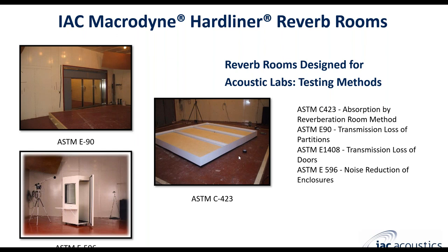The idea is to have speakers producing sound in this reverberation room. Those speakers are amplified by the reflections in the room, and the goal is to have as much echo or reverberation as possible to allow the sound to be evenly distributed across the entire volume. In theory, no matter where you put a microphone, you should have the same sound pressure level measurement inside a perfectly reverberant room. Another common testing method is ASTM E90, which measures the transmission loss of partitions — done with two reverberation rooms, one on each side of a partition in the middle, which is the device under test.